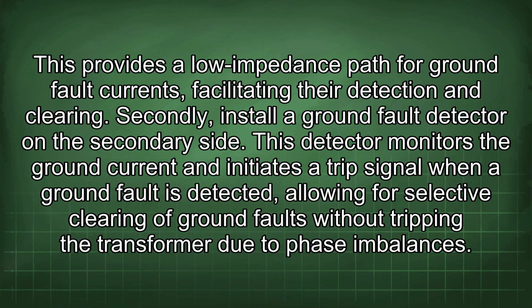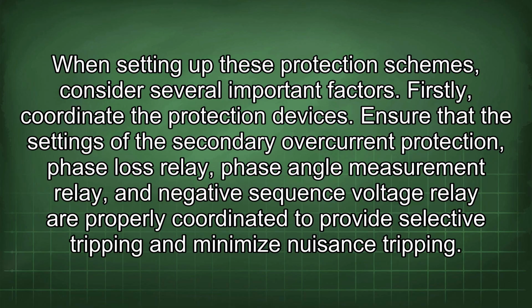Secondly, install a ground fault detector on the secondary side. This detector monitors the ground current and initiates a trip signal when a ground fault is detected, allowing for selective clearing of ground faults without tripping the transformer due to phase imbalances. When setting up these protection schemes, consider several important factors. Firstly, coordinate the protection devices.